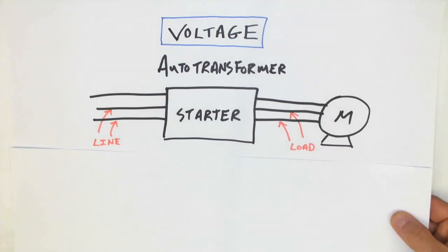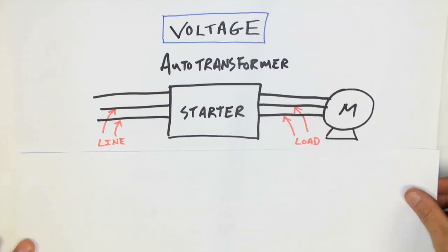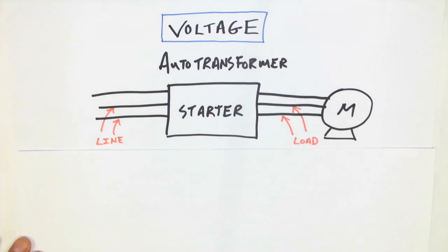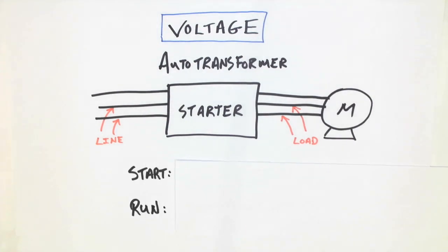What about the voltage though? Well, we have both sides of this starter, the line and the load side. When we're looking at the motor starting, the line side should still be 600 volts, but the load side will be the reduced value of 390. During run, we would expect 600 volts being applied on both the line and the load side of this reduced voltage starter.